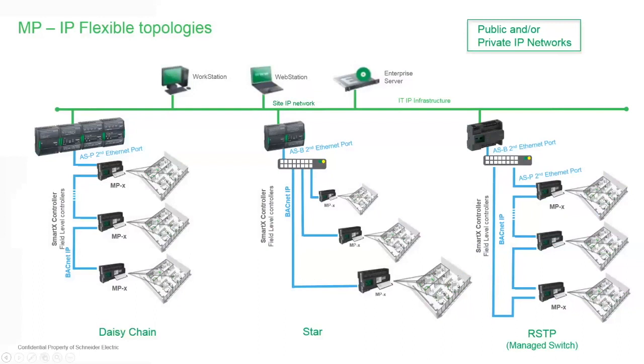Let's say there are 30 controllers on this trunk and you lose the second one—you actually lose everything downstream of it, so they'd all go into standalone communication to the spaces they serve. You might not want that for laboratory settings or other really important areas, so you can home run and do redundant cabling with the approach in the middle.